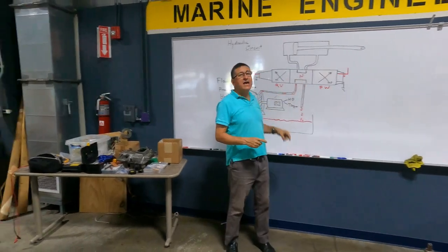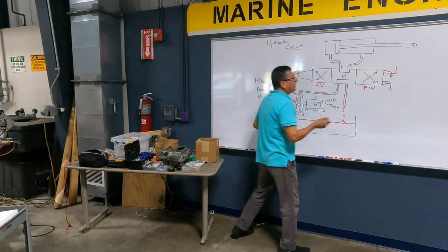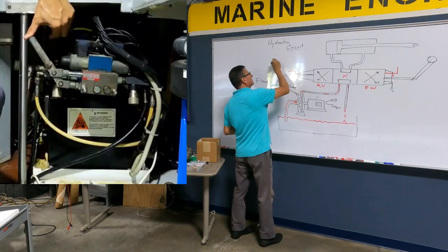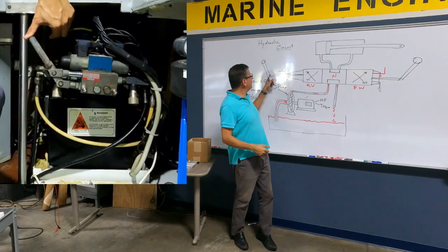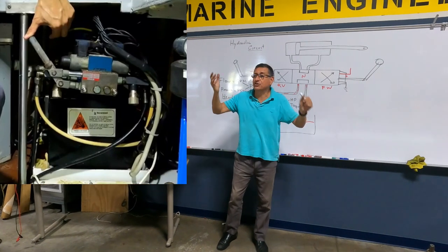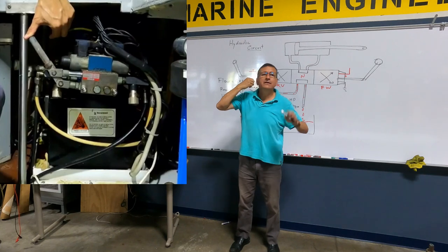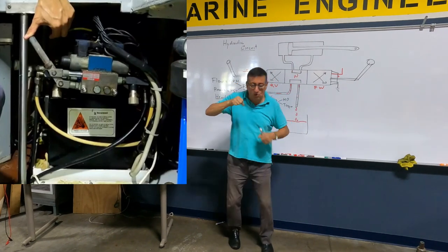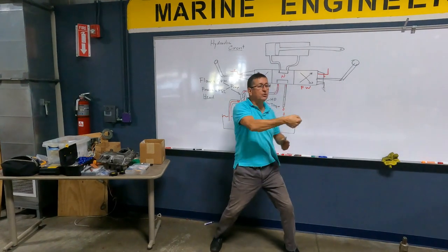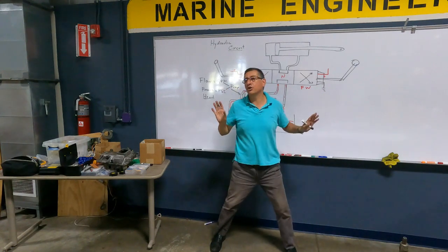And in some of them, you see the solenoid on each side, and also you see one handle, like this, one handle. What is the function of those handles? If the solenoids are not working because the switch is broken or something like this, the captain says to the engineer, hey, my friend, the windlass goes down but not up. And you go in the engine room and you select, the third one is the windlass. And with your hand, you activate up or down, because the solenoid is broken.